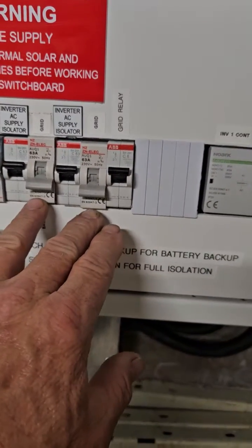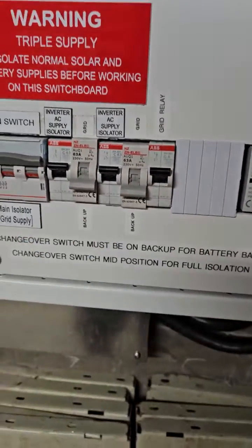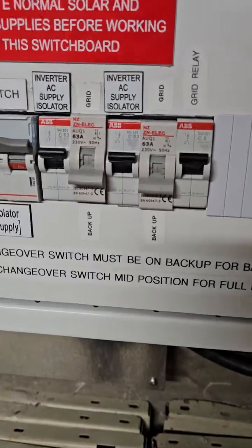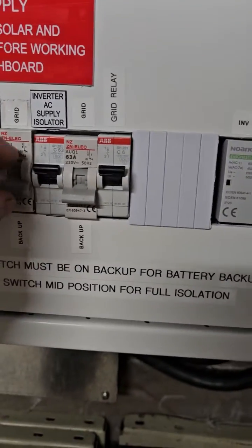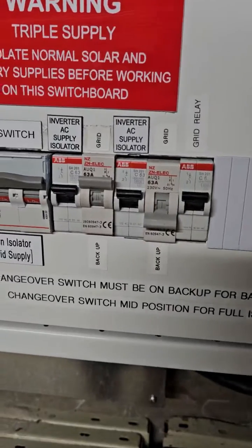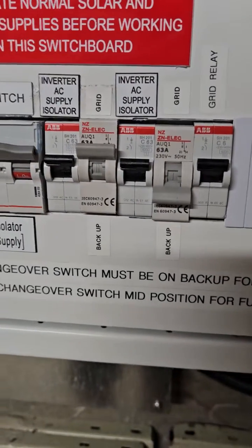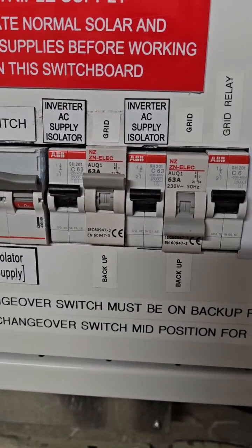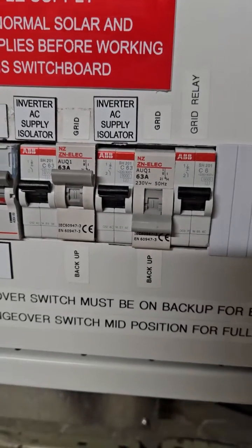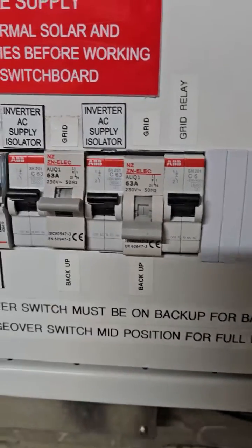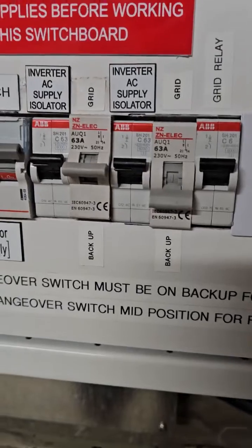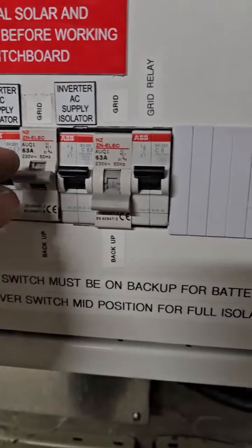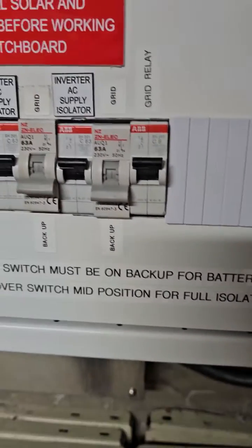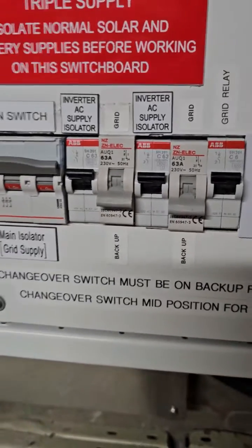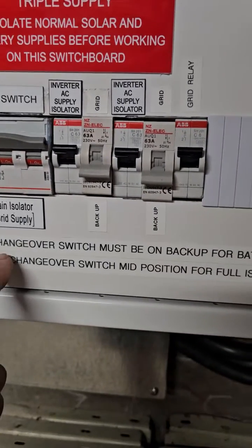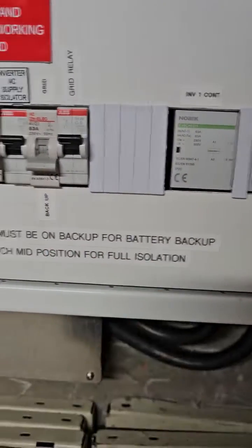Now we have changeover switches, 1 and 2. They're a 3-position switch. When they're in the grid position, or up position, it's not working - it will not work in off-grid mode. In the center position, everything is off - not feeding from the solar, not feeding from the grid. And in backup position, it'll be feeding from the battery system. There are notes here about the changeover.